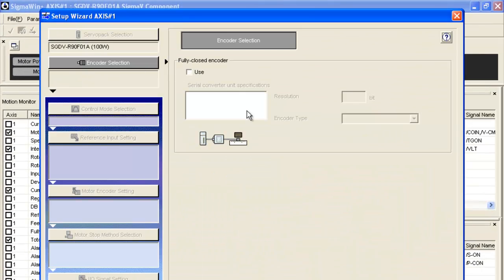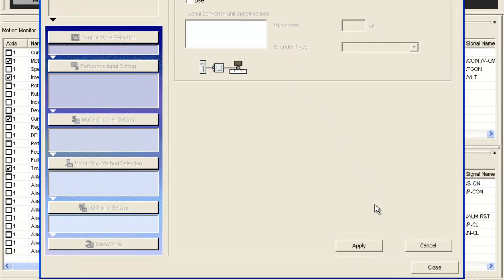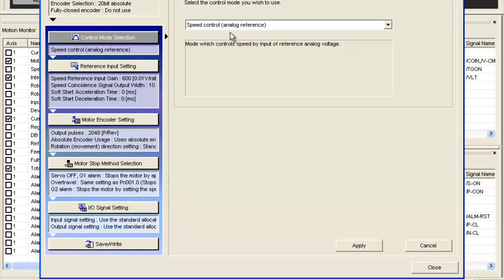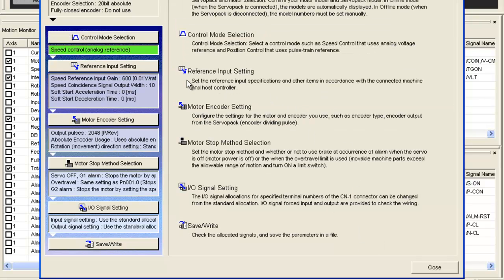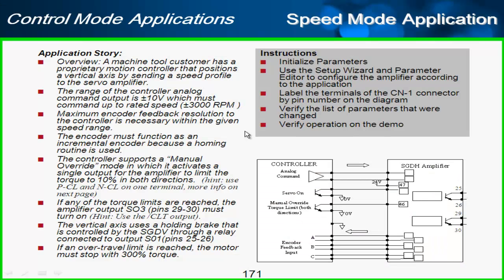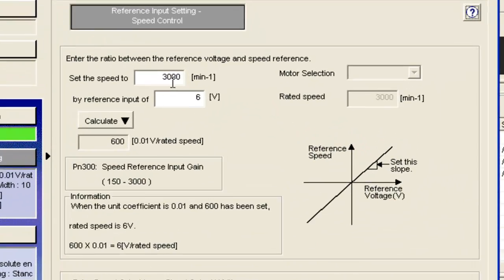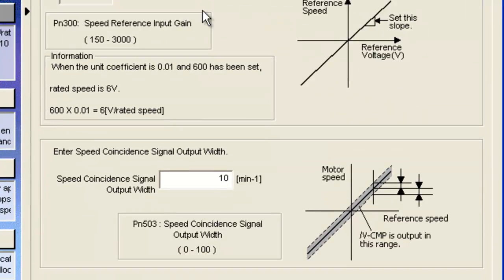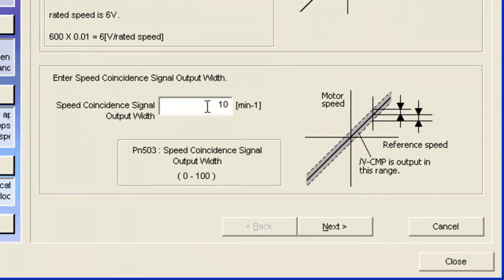I'll start with my encoder selection — I'm not using the fully closed encoder — and I'll choose my control mode as speed control and apply that. Next is the reference input setting: the application states that we'll have 10 volts commanding 3,000 rpm. So I'll enter 3,000 rpm (min⁻¹ is rpm) and 10 volts from the controller, which calculates the parameter for us.